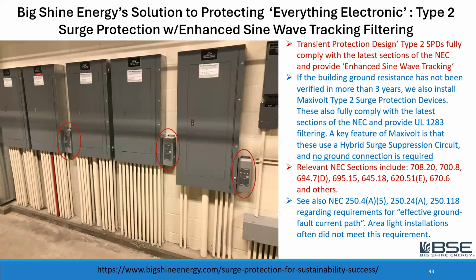Now, I did mention that the National Electrical Code is starting to catch up with requirements for Type 2 surge protection. And here on the screen, you can see some of the relevant NEC sections, but you should do your own research. Just take this for education purposes. And then also see the sections and subparts of NEC 250 that talk about the effective ground fault current path. This is where you'll see that it's no longer adequate to just rely on the dirt between lighting poles, for example, back to your source.